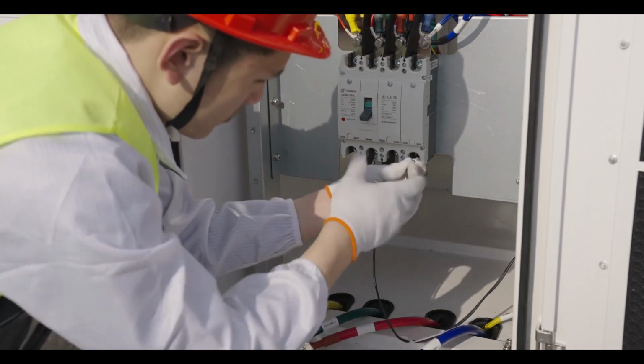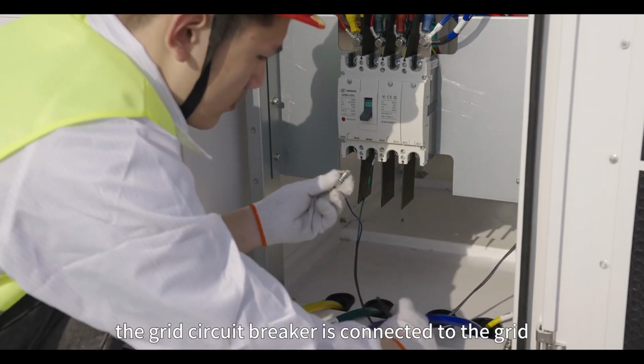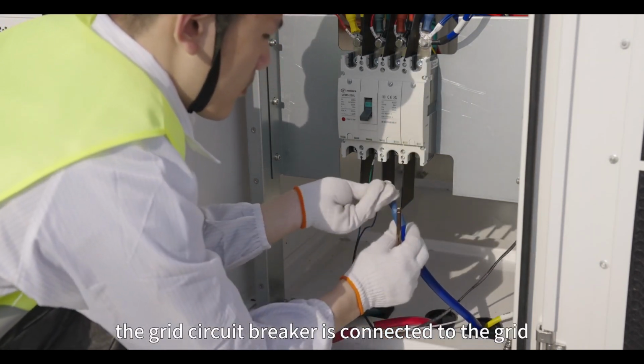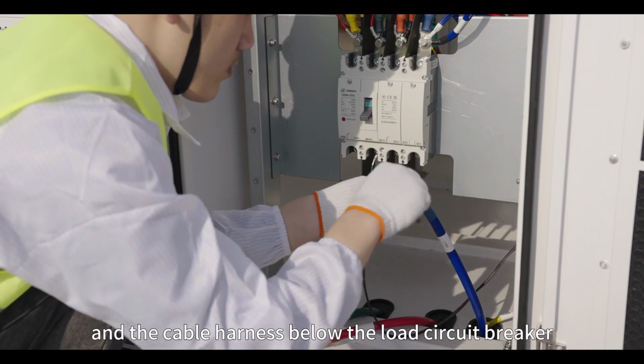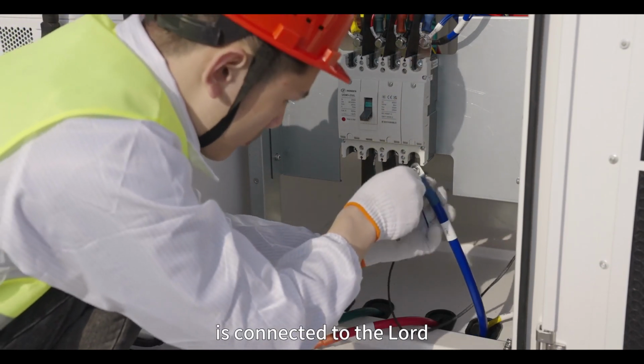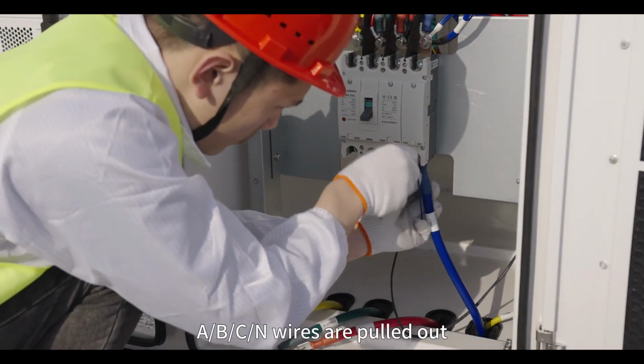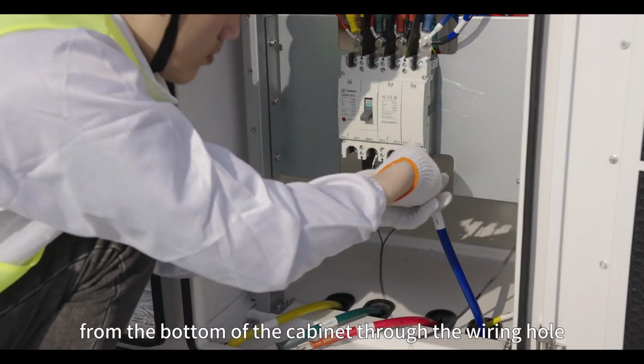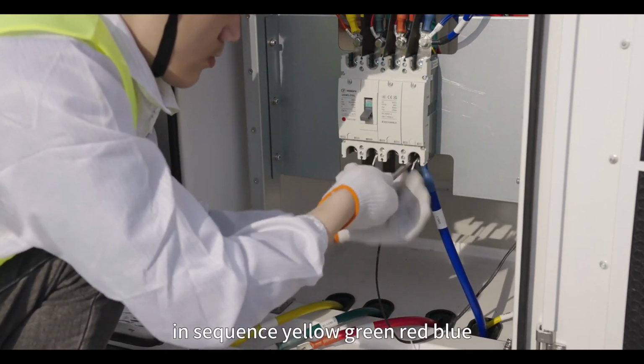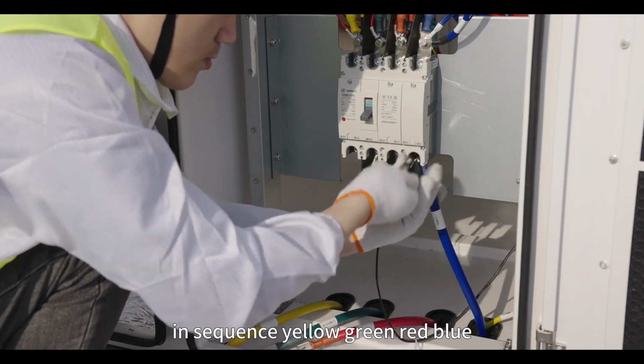The cable harness below the grid circuit breaker is connected to the grid, and the cable harness below the load circuit breaker is connected to the line. A, B, C, and N wires are pulled out from the bottom of the cabinet through the wiring hole in sequence: yellow, green, red, blue.